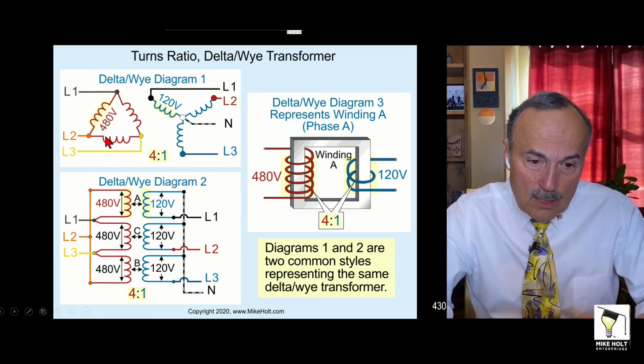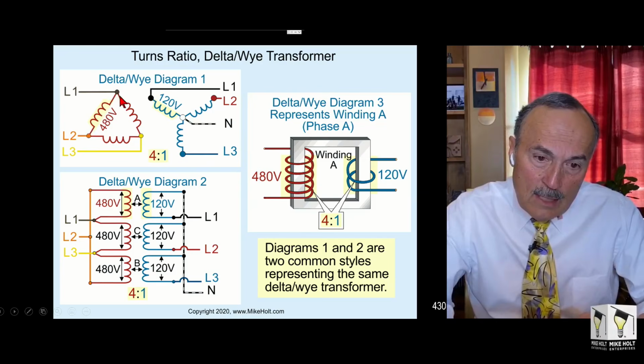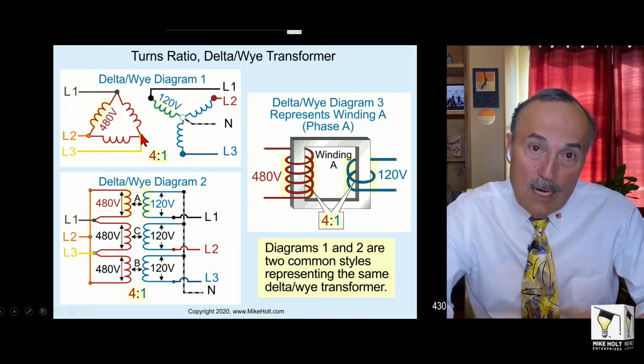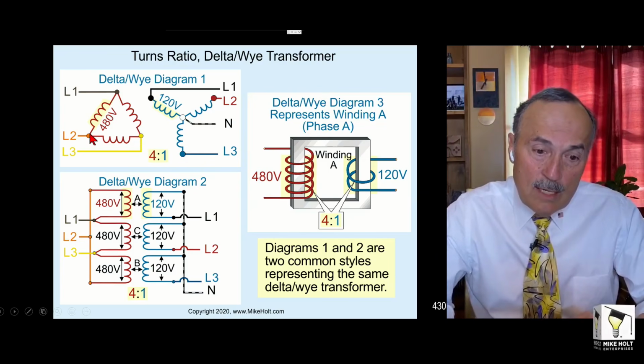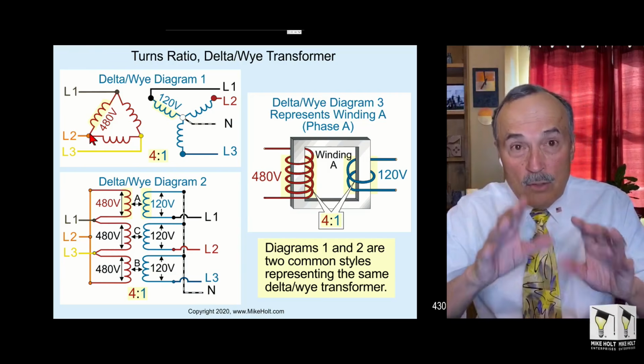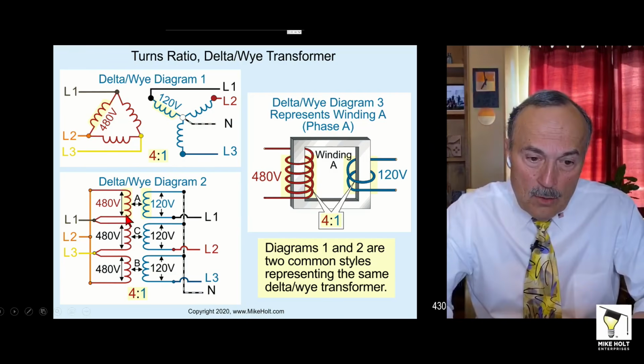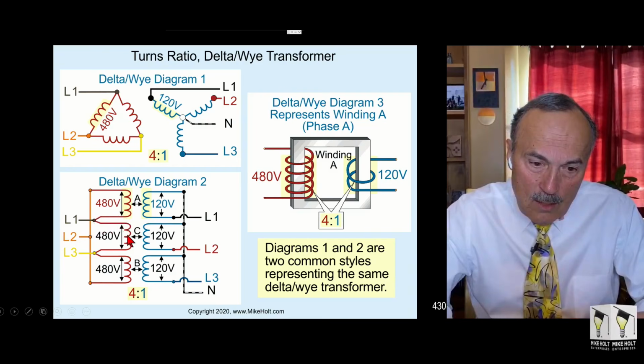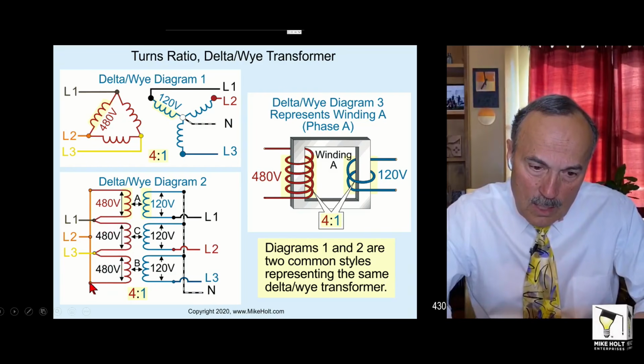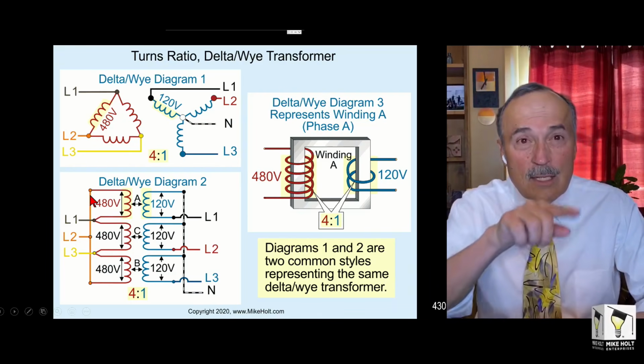So then what you do is this. This winding is connected to that corner of the winding, which is connected to that corner of the winding, which is connected to that corner of the winding. If you watch this video later on, you can slow it down and stop it. You'll see that this connection is to that winding, it goes to this winding, it goes back to this winding. They're actually in series with each other.